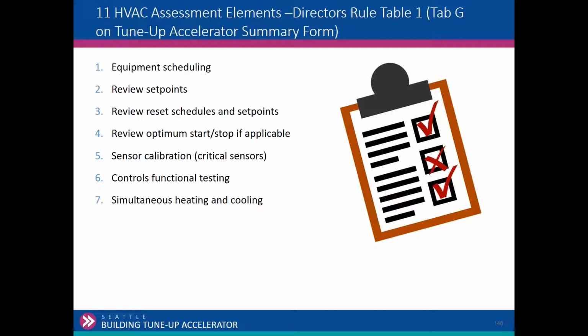Simultaneous heating and cooling. A VAV system is a system that's designed for simultaneous heating and cooling. But if there are obvious situations where you have systems fighting each other, like big box retail, where you've got one rooftop unit in cooling and one rooftop unit in heating, there's an opportunity there to control them. I know a lot of the big retailers now are just averaging the temperature in the store and using one average temperature as their input. So is there an opportunity to minimize simultaneous operation? Or you've got electric heaters and electric air conditioning and there's no deadband and they can run at the same time.